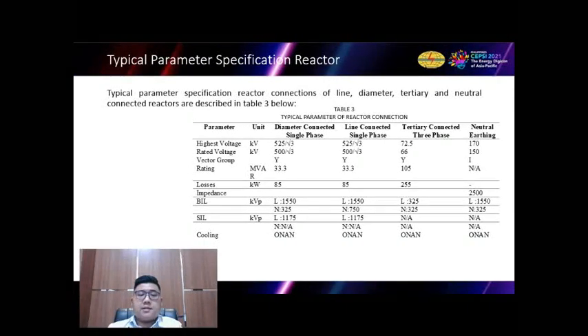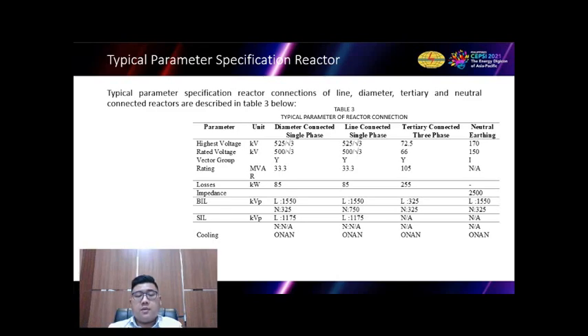Now we continue to the next slide. In this slide, we are talking about the typical parameter specification of reactor. The typical parameter specification of the line, diameter, tertiary, and neutral connected reactor are described in table 3 below. The parameters of the reactor consist of the highest voltage, rated voltage, vector group, rating, losses, impedance, BIL, SIL, and the cooling.